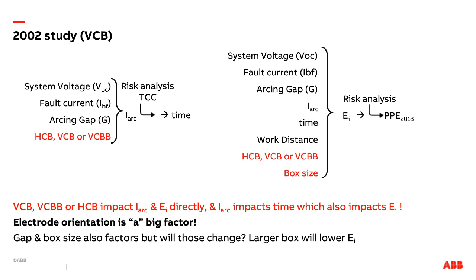The good thing is that that's a factor that can be decided upon by a simple physical inspection of the equipment, of the conductors, of whatever the exposed conductors that you think could have an arc flash. All you have to do is look at them, look at the direction of the power going into the potential arc. Is it horizontal? Is it vertical? Is it going to run into a barrier and sort of crash into something, or is it going to just flow fairly easily? And that can be done by inspection. You don't need a PhD in obscure sciences to figure that out.